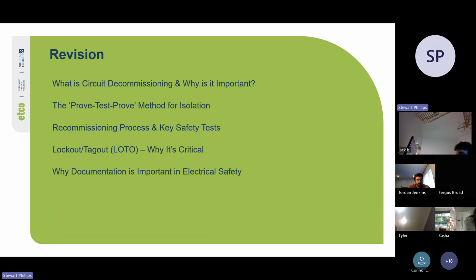I like that - prove you didn't break your meter. Yep, yep, so you guys are getting it. Prove the tester is working on a known live source, test the circuit to ensure it's de-energized, and then the correct terminology is prove the tester again on a known live source, but I like the term of prove you didn't break it while you were doing your testing.